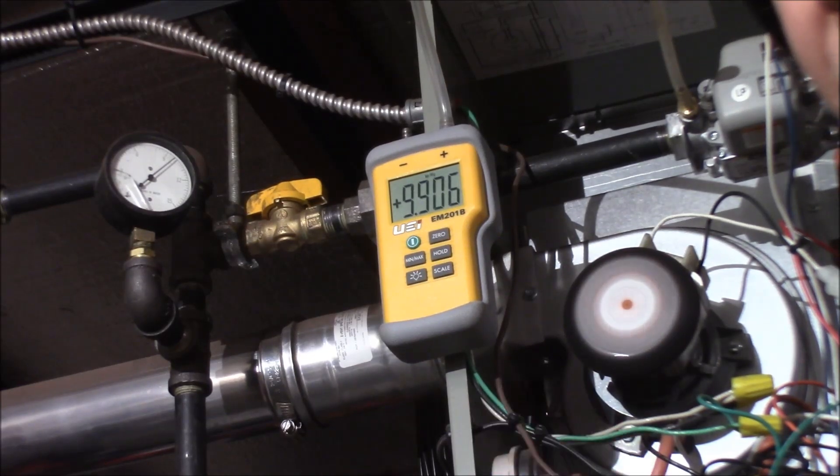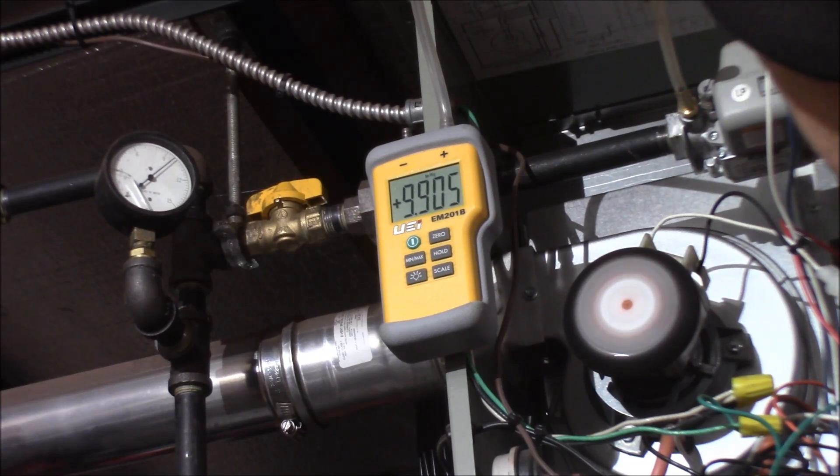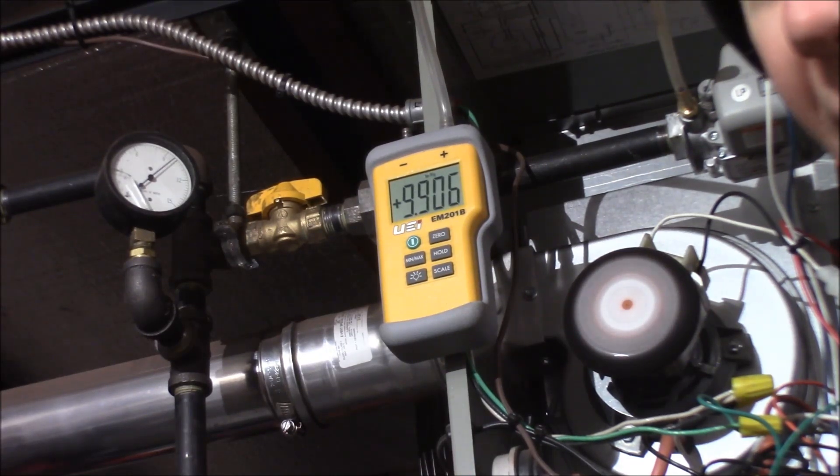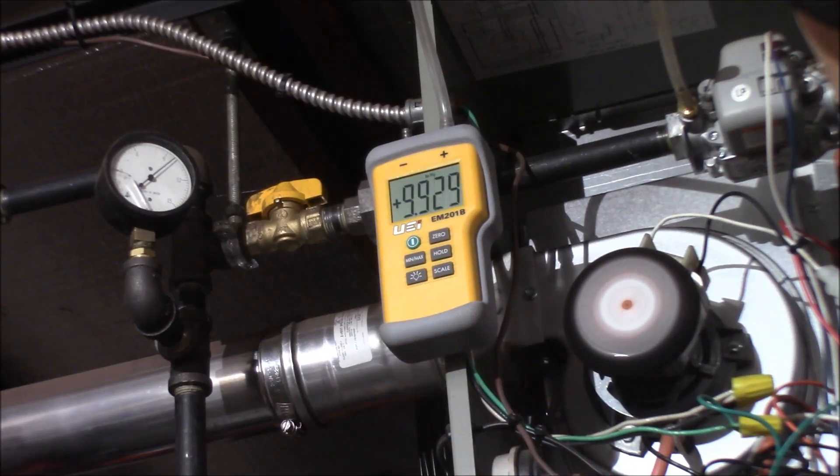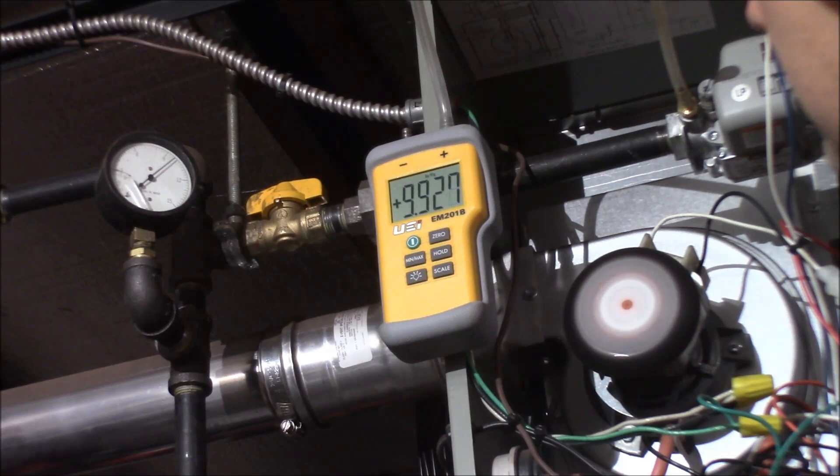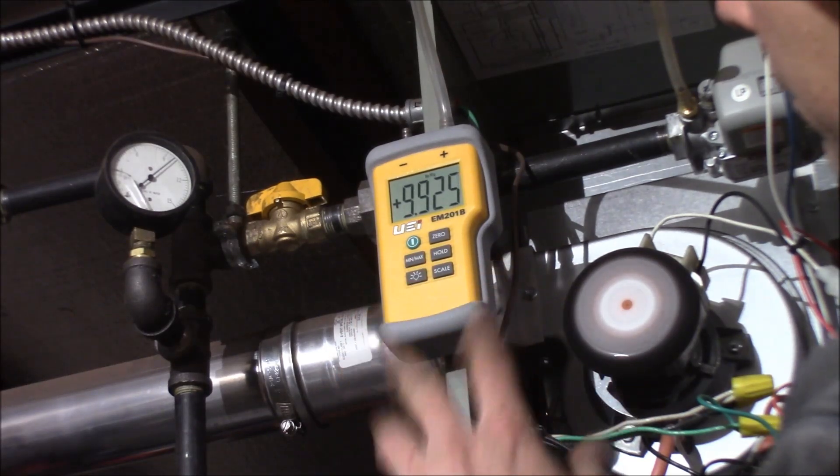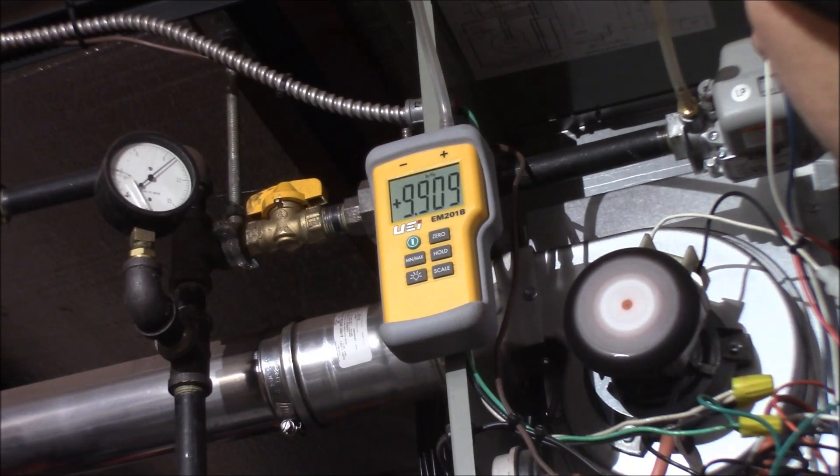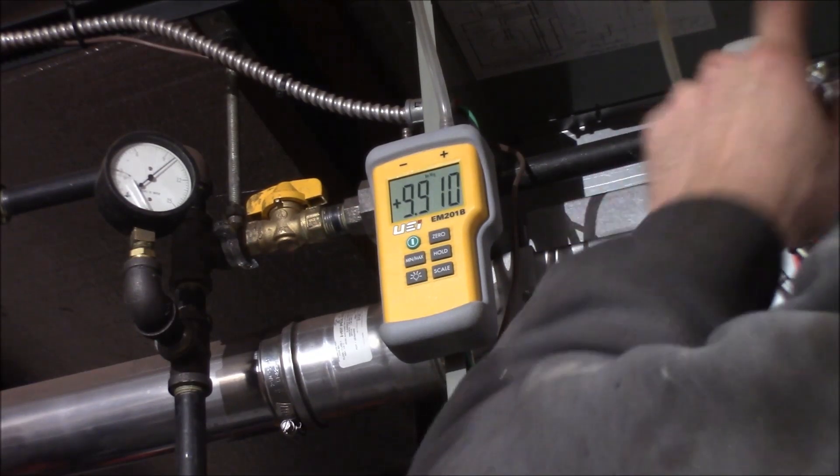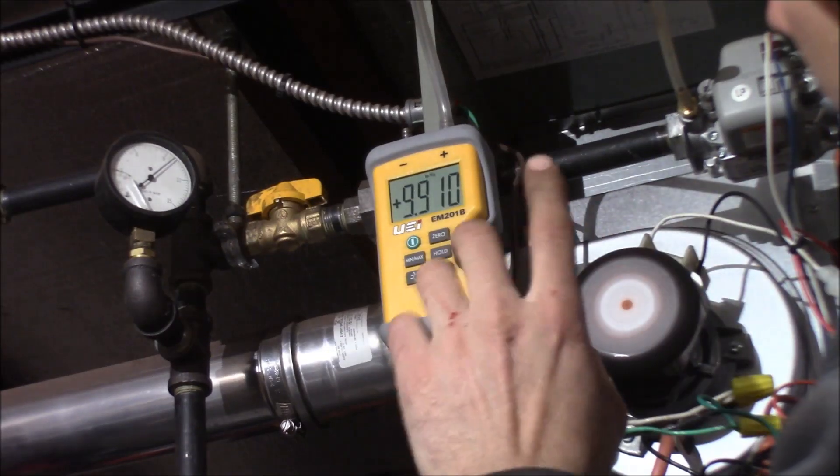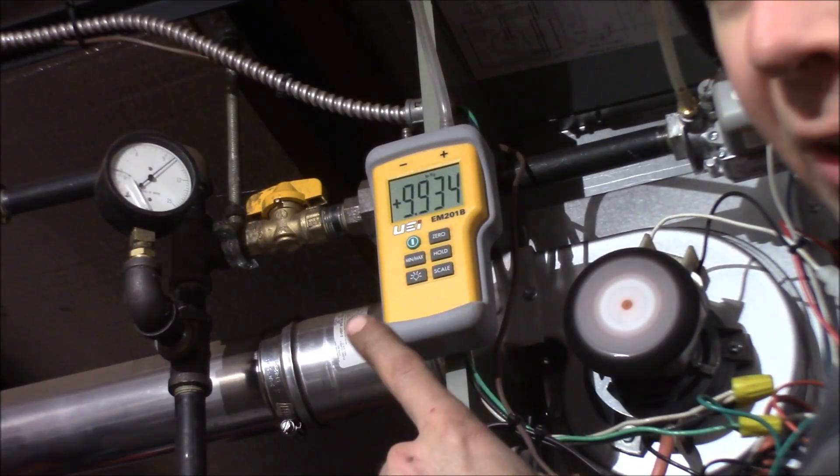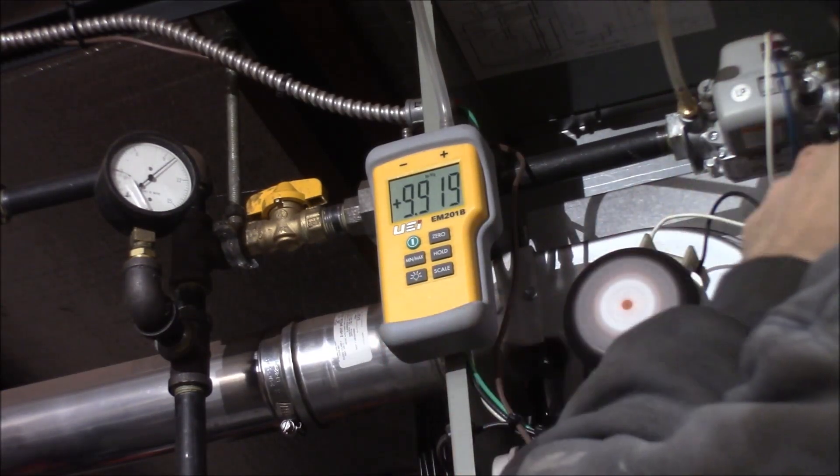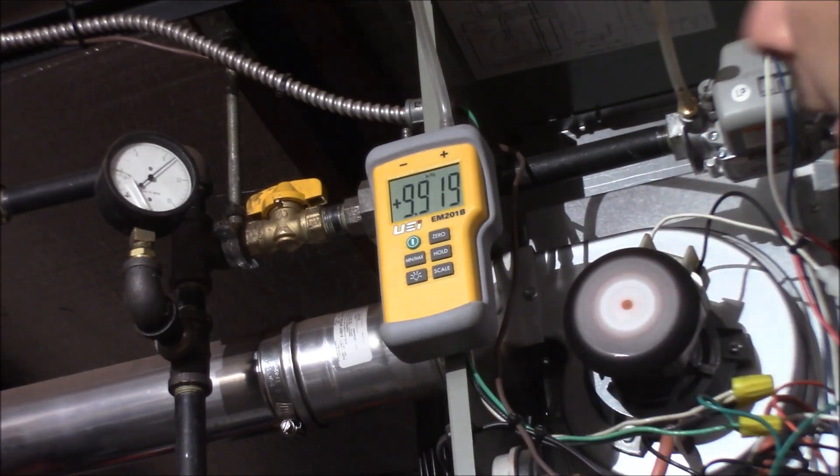So I'm just a shy lean. And I can go out and I can adjust the outside regulator just a little bit to bump my pressure up. So we can see here running 9.925, or just a hair lean. I can go in the other port, but I probably should bump it up outside just a little bit to get it up to 12.